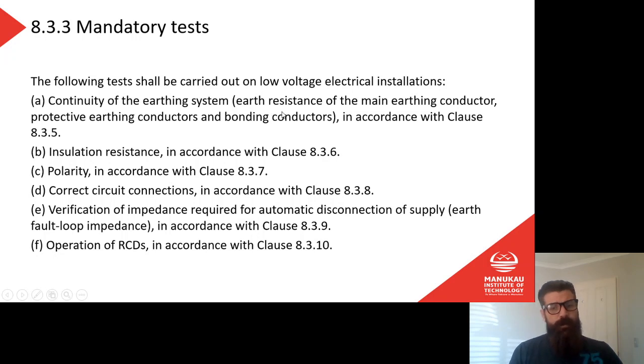Continuity of the earthing system. It's the earth resistance of the main earthing conductor, protective earthing conductors and bonding conductors. So we probably don't yet have much idea what an earthing system is, or how it works, or what it's for. What I can tell you in very simple terms is the earthing system is all the green wires, and that, without going into too much detail, is one of our primary safety systems within an electrical installation. So we need to know that that safety system works.